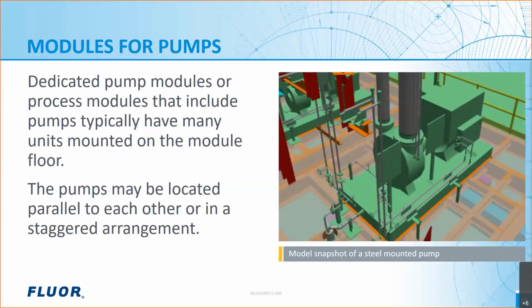Here is a 3D image of a modularized pump unit. Dedicated pump modules typically have several pumps in different services installed on its floor. Multiple units are strategically located based on assessment of their dynamic behavior, operating and maintenance access requirements, and human factor design aspects. Taller vertical inline pump units have reduced headroom for maintenance. Their total installed height is checked against elevation of the first deck on the module from the module's floor. The other types of structural steel mounted equipment, such as positive displacement blowers, centrifugal fans, and rotary screw compressors, are usually part of process or packaged equipment modules.